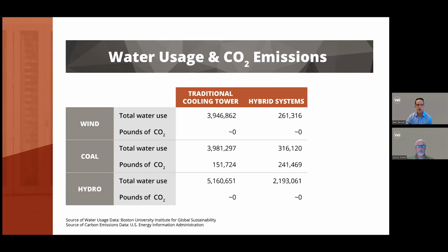So when you look at that hybrid system, the water use from power becomes a bigger percentage and a bigger absolute number. But you'll see that the total water use is still dramatically lower than the cooling tower solution, even once I factor in the extra water needed to create the electricity.